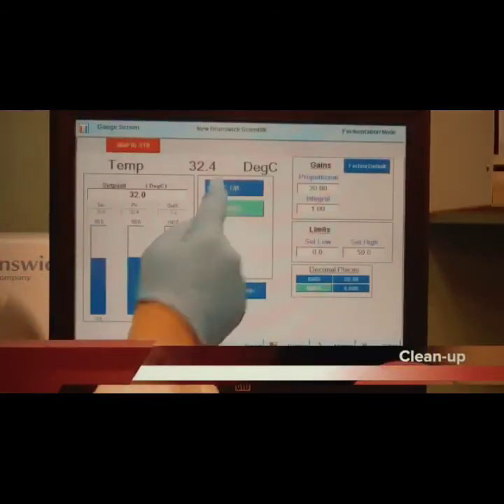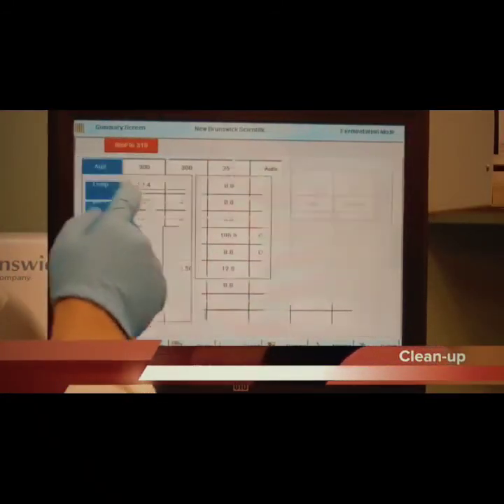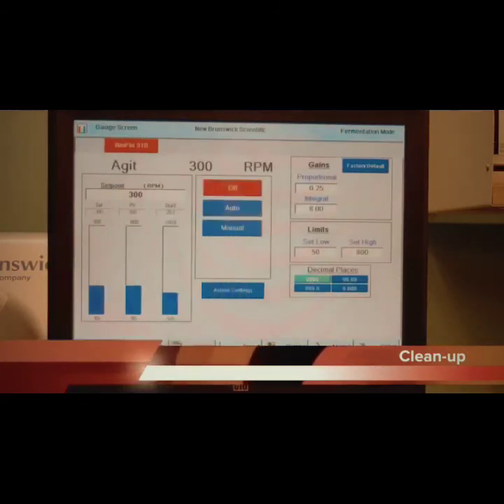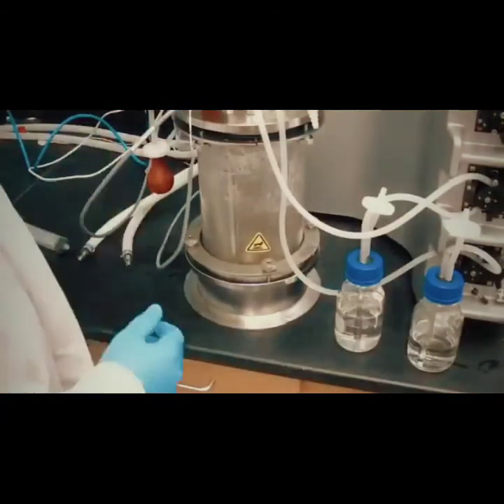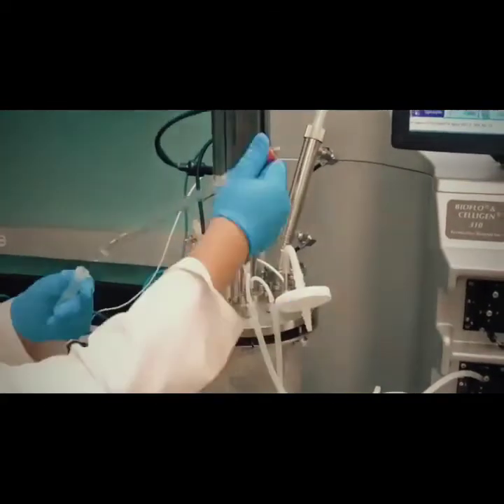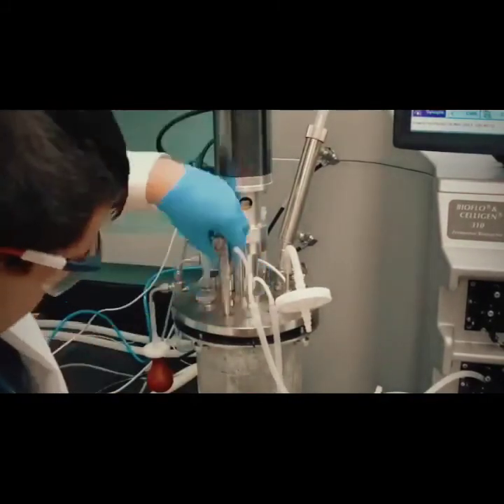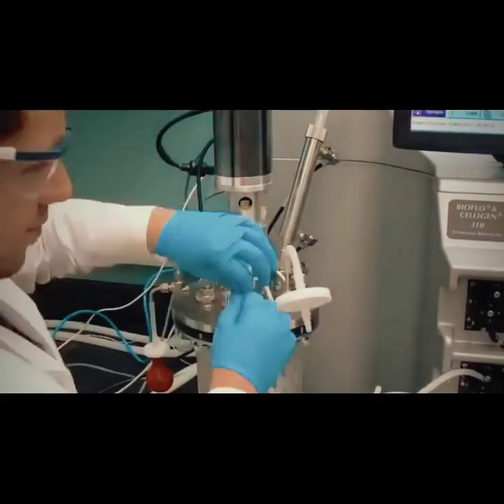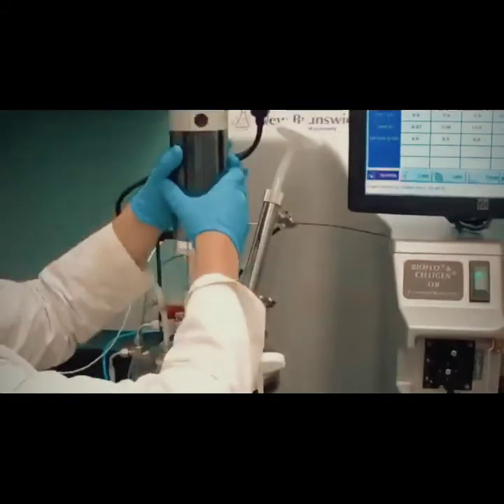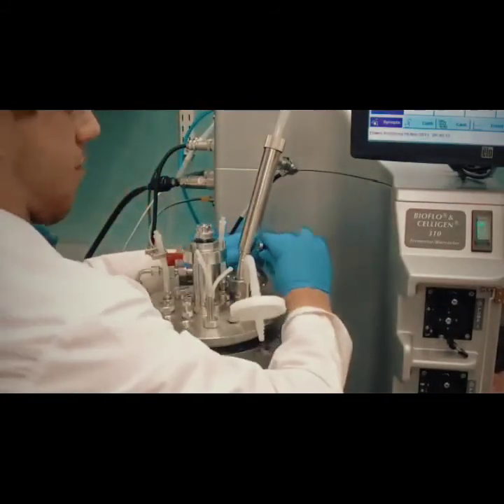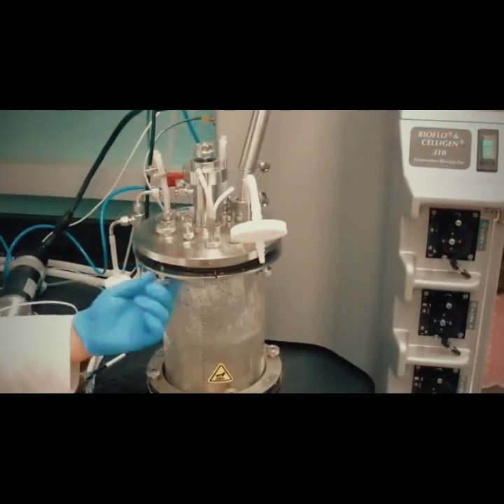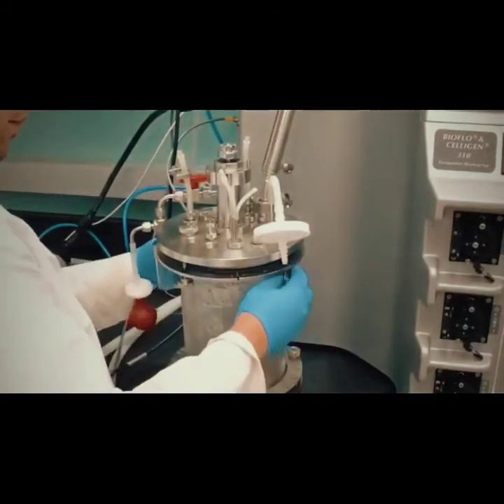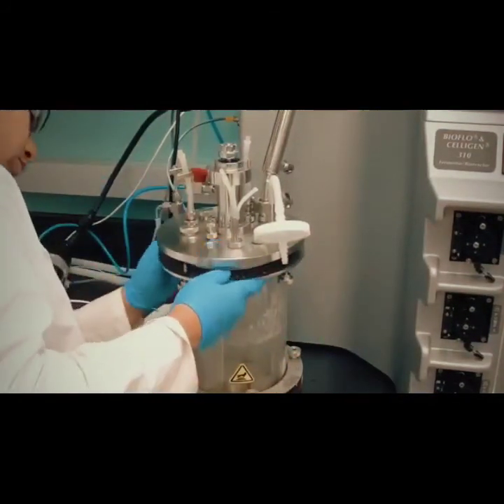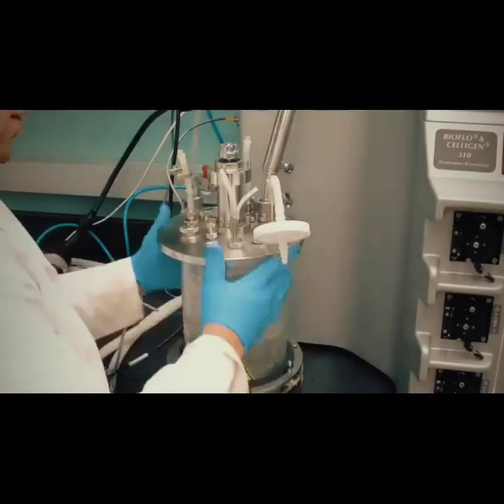Set temperature control to off. Set agitation to off and remove the drive motor. Disconnect, remove, rinse, and store all lines, probes, and cables. Loosen the nut holding the sterile sampler in place and lift out the assembly for easier cleaning. Wipe down the metal tubing and rinse out with distilled water, being careful that the filter does not get wet. Disconnect. Wipe everything else down and clean it up.